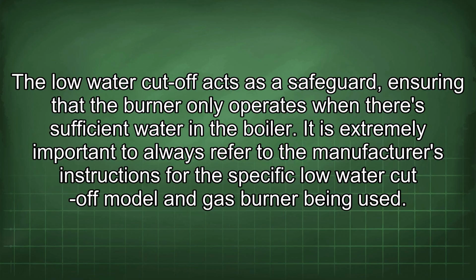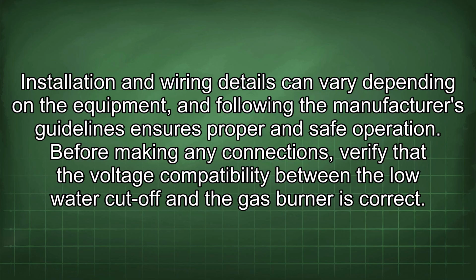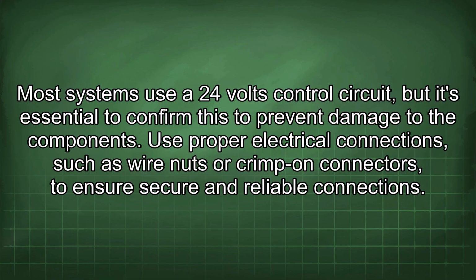It is extremely important to always refer to the manufacturer's instructions for the specific low-water cut-off model and gas burner being used. Installation and wiring details can vary depending on the equipment, and following the manufacturer's guidelines ensures proper and safe operation. Before making any connections, verify that the voltage compatibility between the low-water cutoff and the gas burner is correct. Most systems use a 24 volts control circuit, but it's essential to confirm this to prevent damage to the components. Use proper electrical connections, such as wire nuts or crimp-on connectors, to ensure secure and reliable connections.